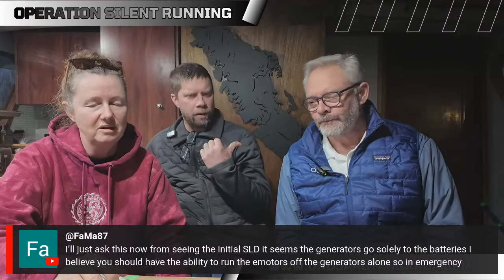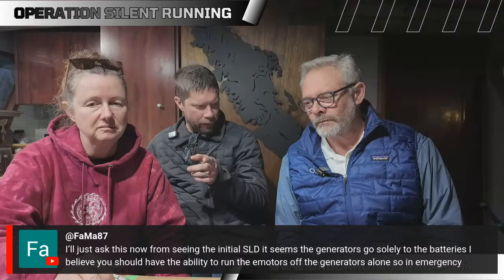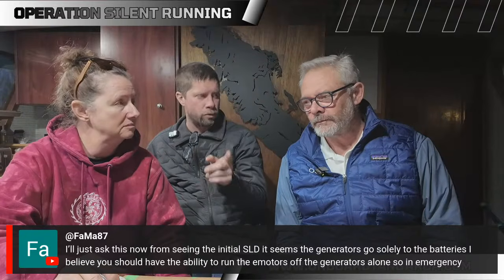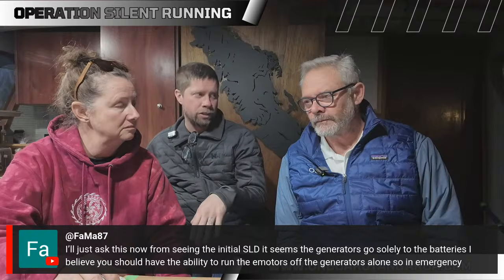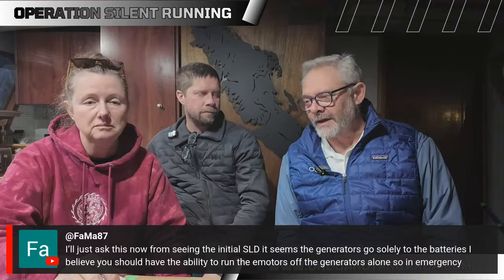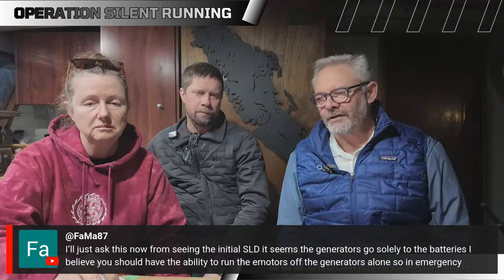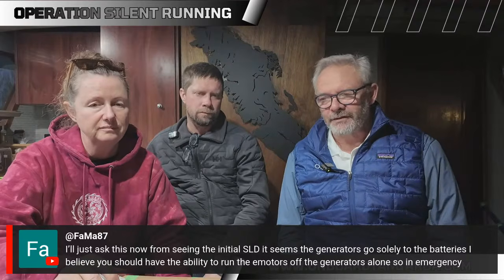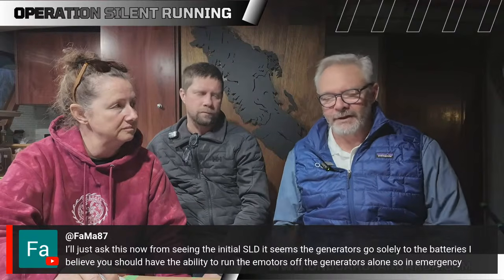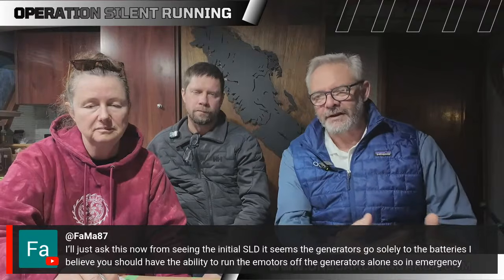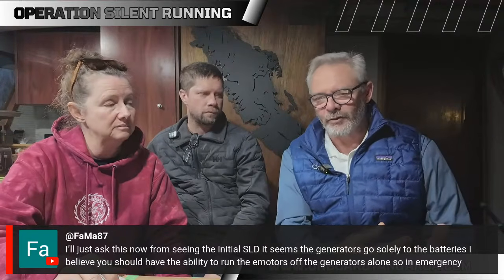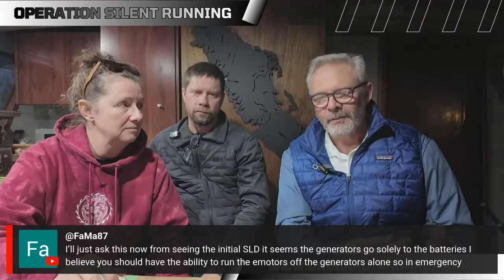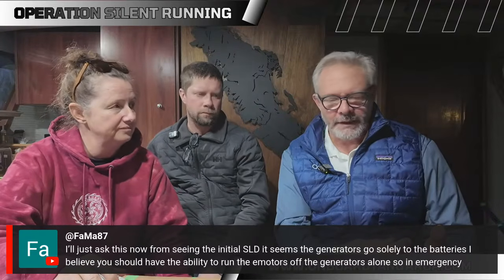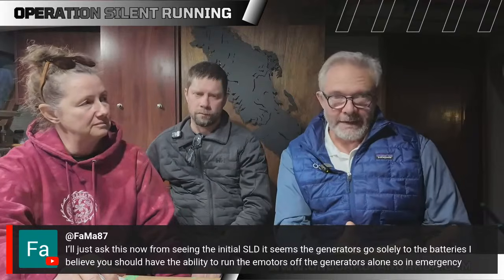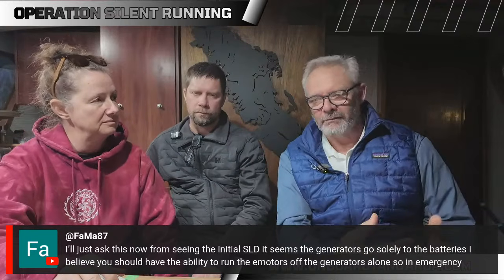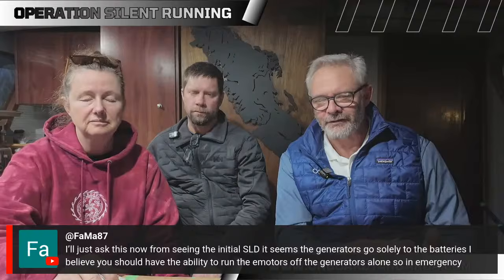He might be talking about being able to electrically still drive the motors from the generators even if you had a battery shutdown. You can, to a certain extent. What we're trying to do is isolate the complexity of the system, and if that's built in as emergency power instead of primary power, it's a lot simpler as a control mechanism to operate and install. But there is absolutely a need in any power boat for some kind of series-parallel element to manage the safe drive of the vessel in an emergency.